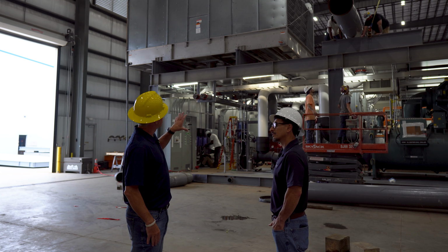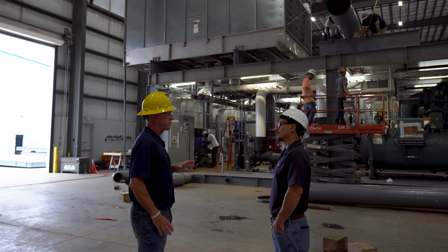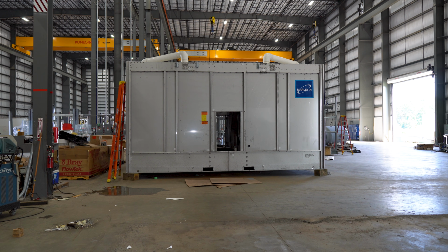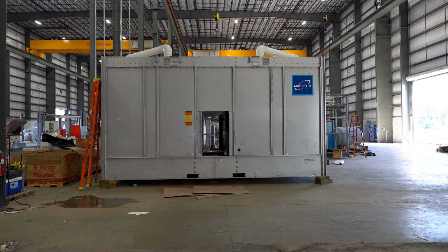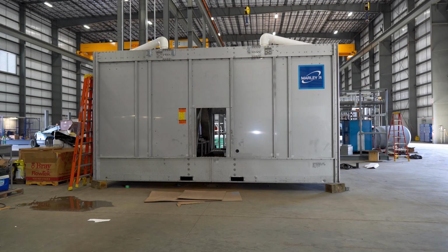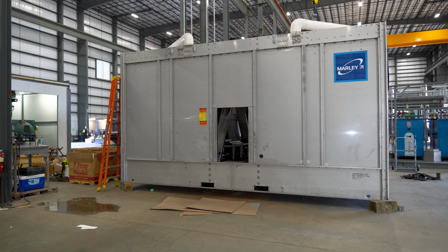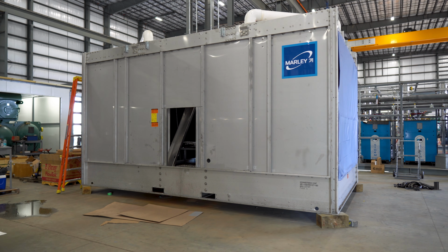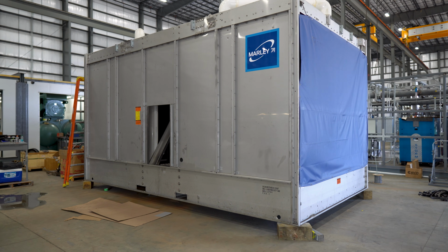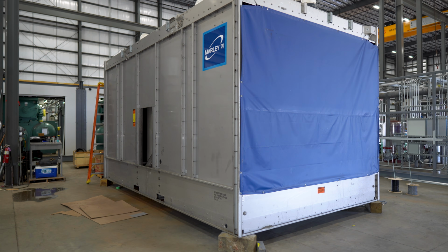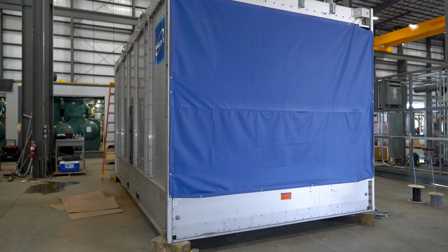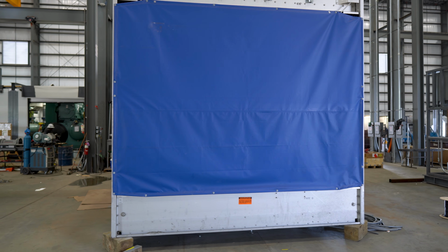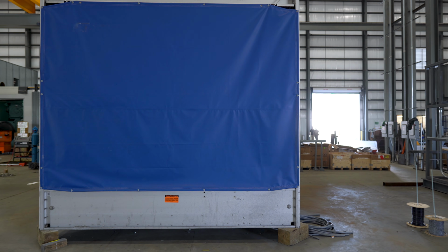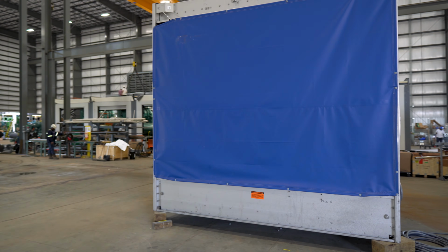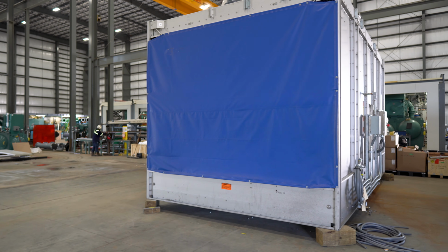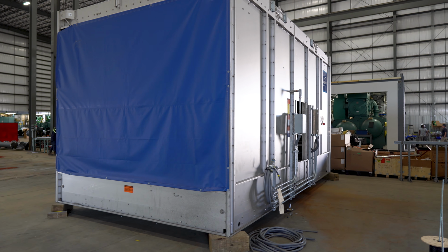The largest single cell cooling tower you can get is roughly about 1,500 tons, which matches perfectly at one module, at 78-degree wet bulb, covering most areas, unless you're going to the Houston area. That's kind of why -- I wouldn't say we maxed out the size with a 1,500 ton module, but it really fits in there nice. It ships down the road easy, with plenty of serviceability. Not to say you can't put larger chillers in there and still have plenty of service, it's just that these line up directly with a single cell cooling tower.